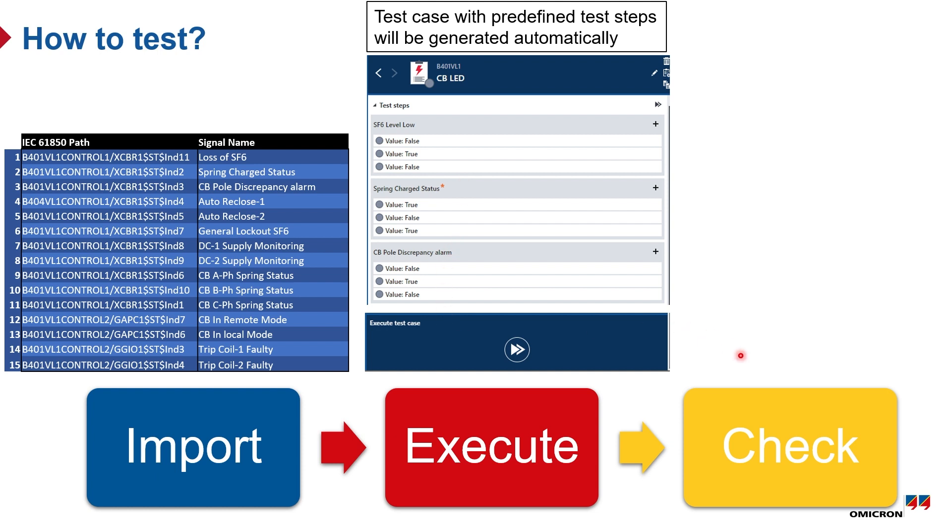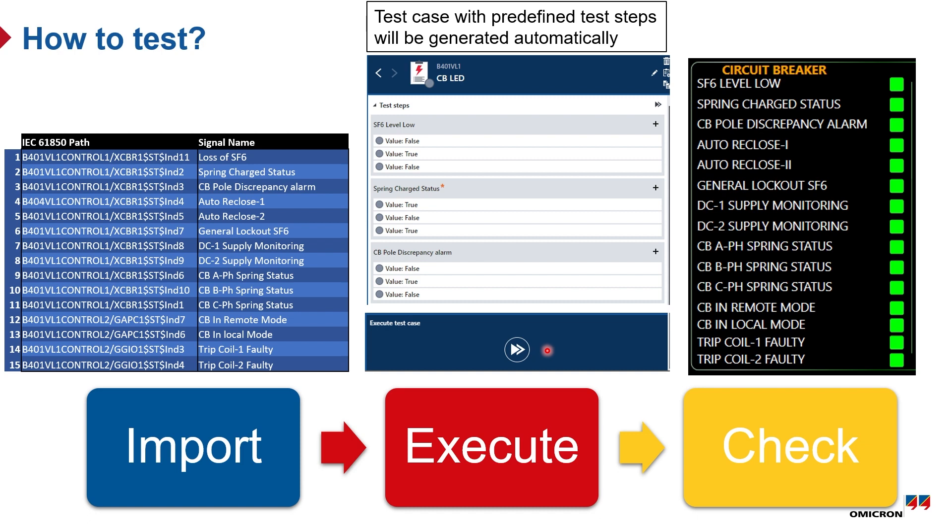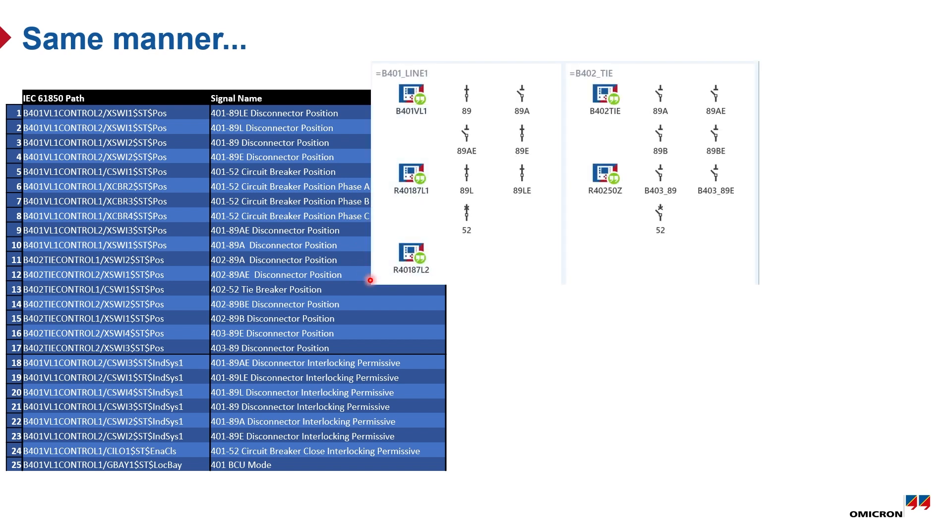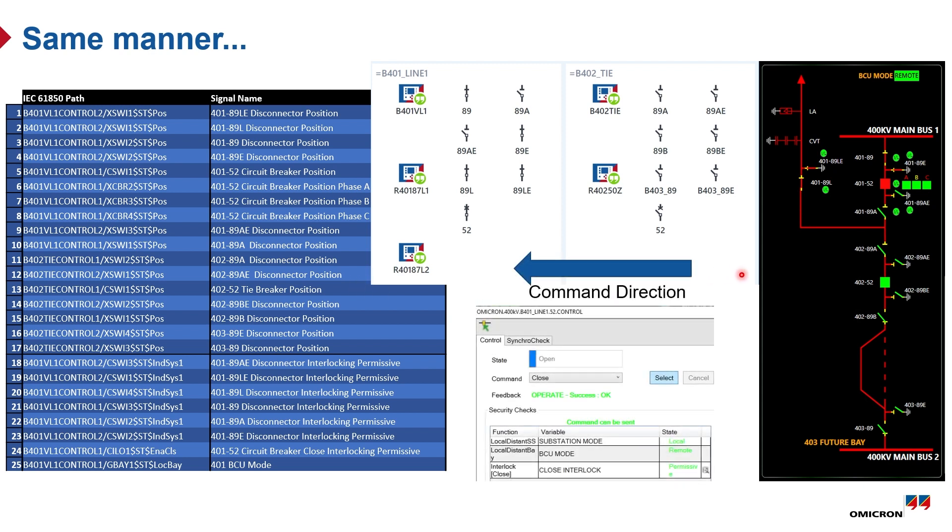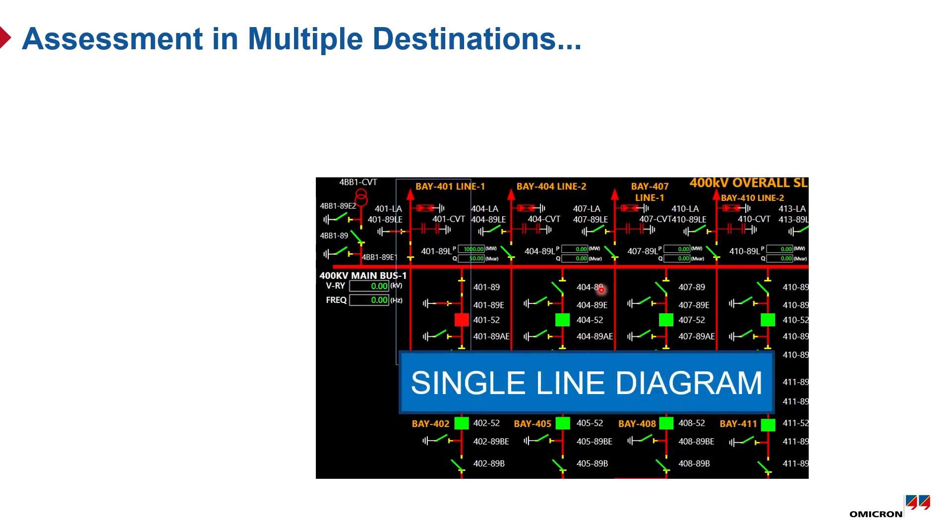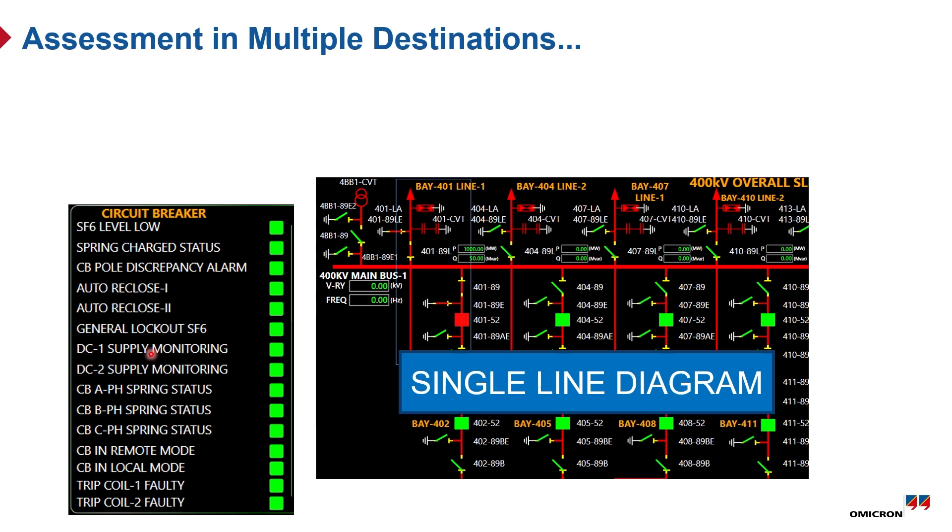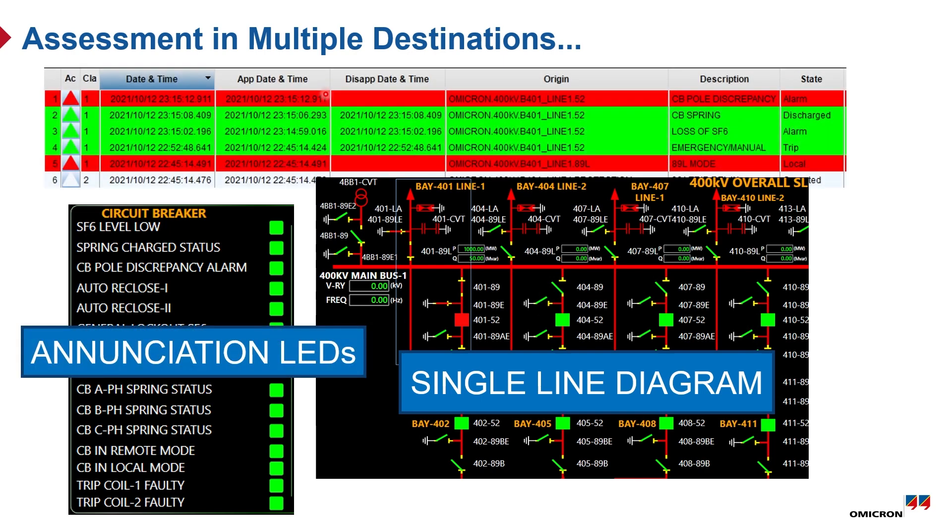Then, as we are used to from Omicron products, to run the test is just a click to the play button. And now as last step, we will check the reaction of our HMI in the corresponding page, like LEDs of a page in this picture. In the same manner, we can test all different signals to verify the communication and correct addressing in different pages, such as mimic diagram of the HMI. Moreover, you can also check the command direction if it's working correctly by issuing some commands from HMI to Station Scout.